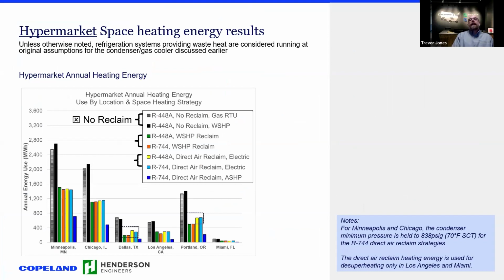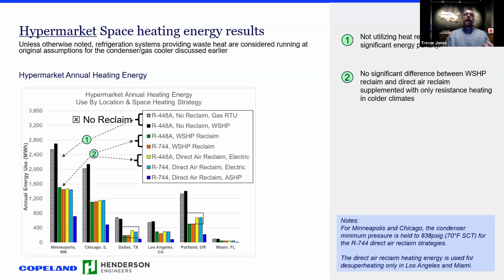So when we looked at the space heating energy results for the hypermarket, it got a little bit different because of the additional heat energy required, because the refrigeration was so much less than what the space needed. So again, the first two bars are no reclaim option. And again, there's a significant energy penalty for not reclaiming the heat. Here we see no real significant difference between water source heat pump or direct reclaim using only resistance heat for supplemental heating in the colder climates, especially.